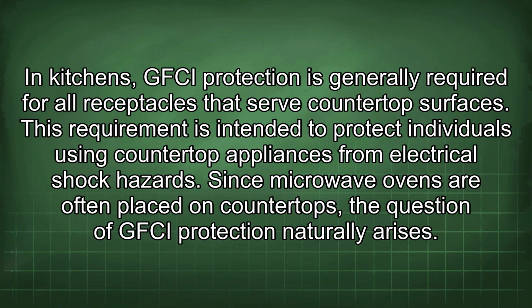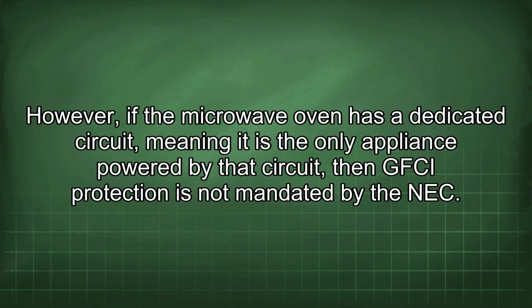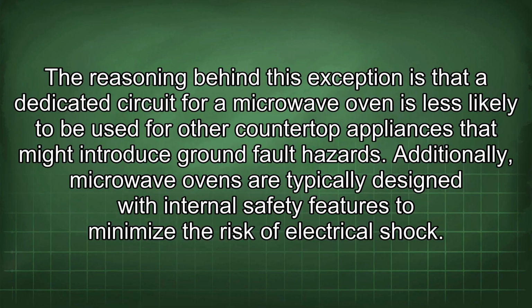In kitchens, GFCI protection is generally required for all receptacles that serve countertop surfaces. This requirement is intended to protect individuals using countertop appliances from electrical shock hazards. Since microwave ovens are often placed on countertops, the question of GFCI protection naturally arises. However, if the microwave oven has a dedicated circuit, meaning it is the only appliance powered by that circuit, then GFCI protection is not mandated by the NEC. The reasoning behind this exception is that a dedicated circuit for a microwave oven is less likely to be used for other countertop appliances that might introduce ground fault hazards. Additionally, microwave ovens are typically designed with internal safety features to minimize the risk of electrical shock.